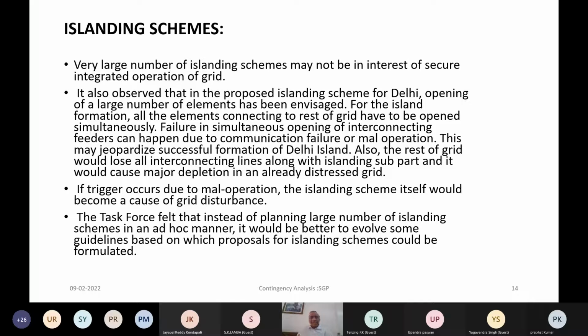When the system has major contingencies and the system is weakened, when any event gets triggered, to prevent total collapse of the grid, it is desirable to split the grid in a controlled manner. This is called controlled isolation. And this controlled isolation can be achieved through a planned islanding scheme. And it was mandated that all the major cities in India should have islanding schemes, so that in case of grid disturbance, power supply can continue without any interruption in the critical areas.